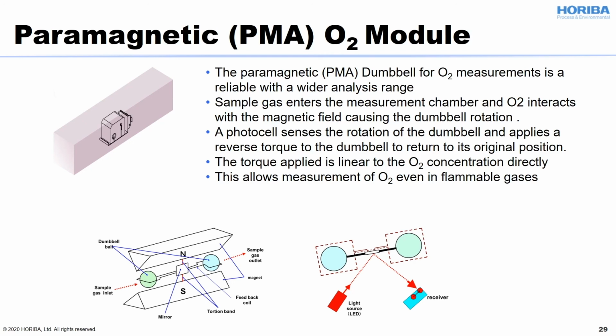This method also uses the strong paramagnetic properties of oxygen. Sample comes into the chamber and O2 interacts with the magnetic field, causing the dumbbell to rotate. A photocell senses the rotation of the dumbbell and applies a reverse torque to the dumbbell to return it to its original position. The torque applied is directly linear to the O2 concentration. But as you can see, the sample gas goes through this, which means all of the sensor material is going to be touching the sample gas. If you have a corrosive component in the sample gas, the PMA is going to be affected.